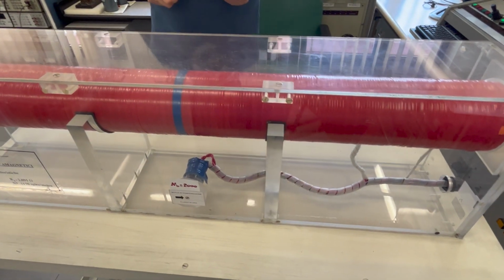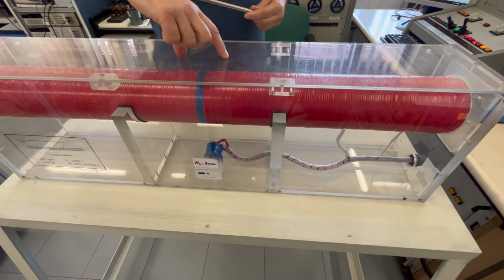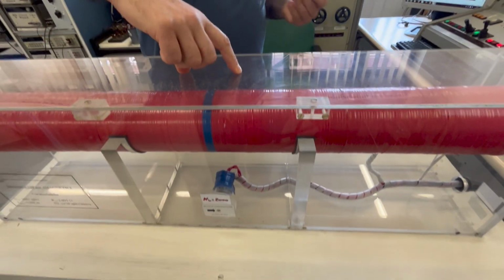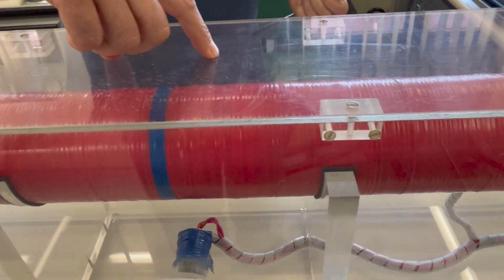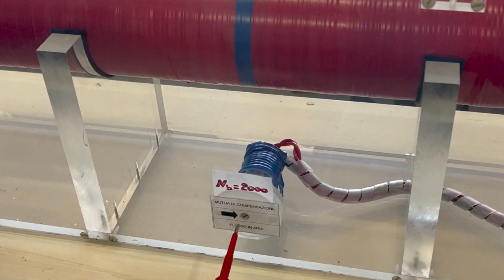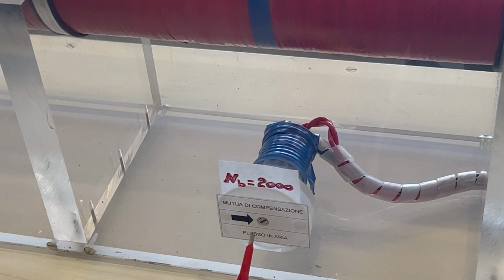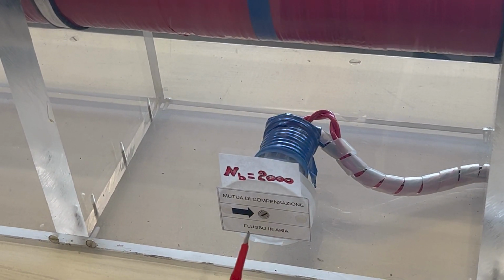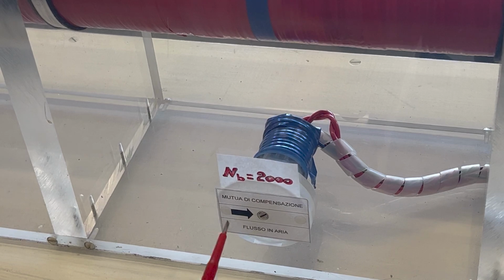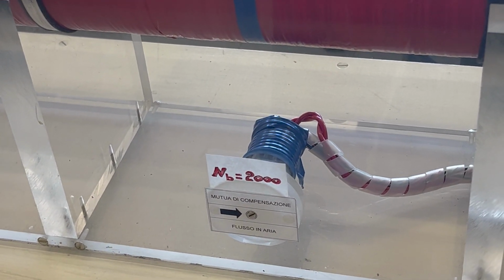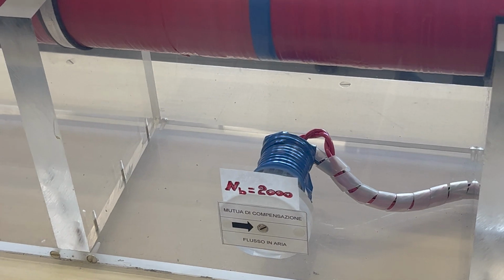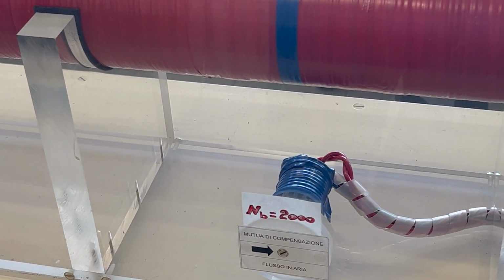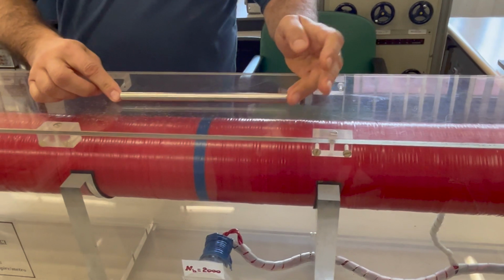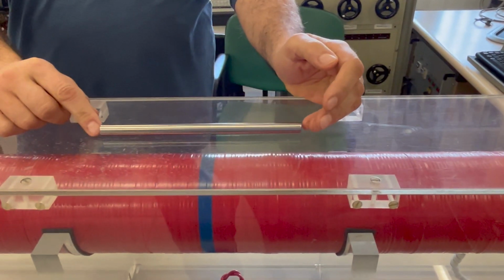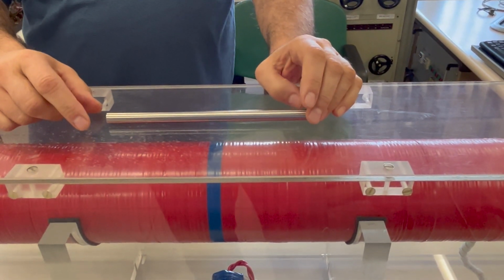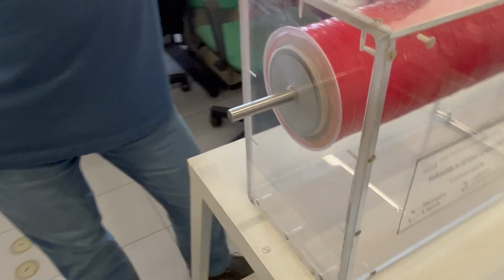In this case, the pickup coil is not directly wound on the sample. Instead, it is fixed in the center of the magnetizing solenoid in correspondence of that blue band that we can see from the outside. An external compensation coil allows to null the signal of the pickup coil when no sample is inserted into the solenoid. The sample is placed inside the solenoid at the central position, so that the pickup coil is approximately at mid-length of the sample.